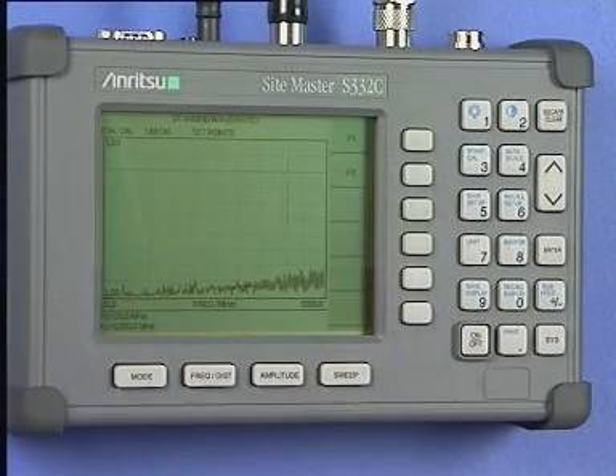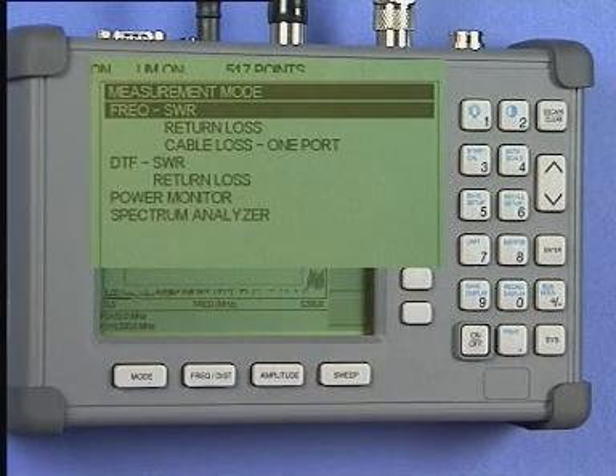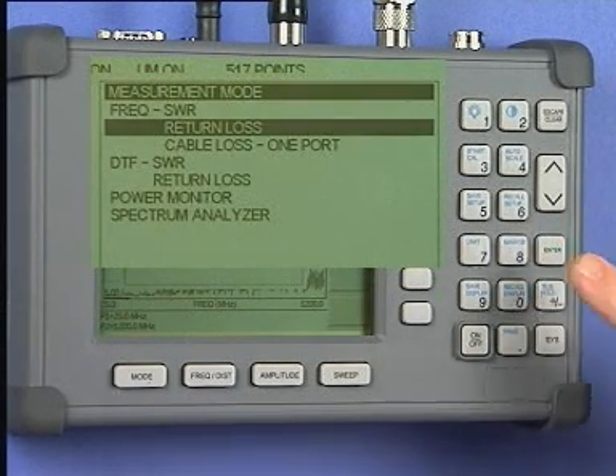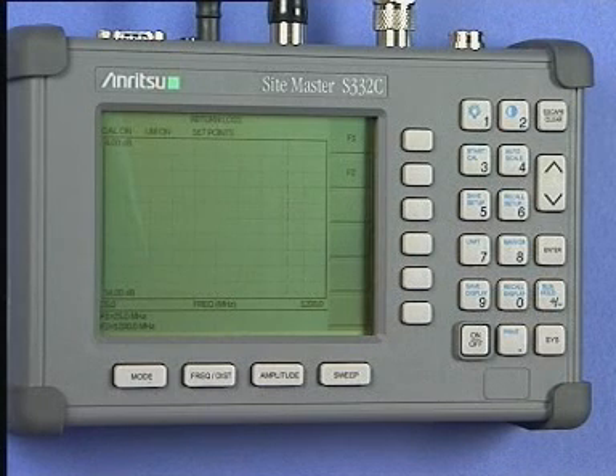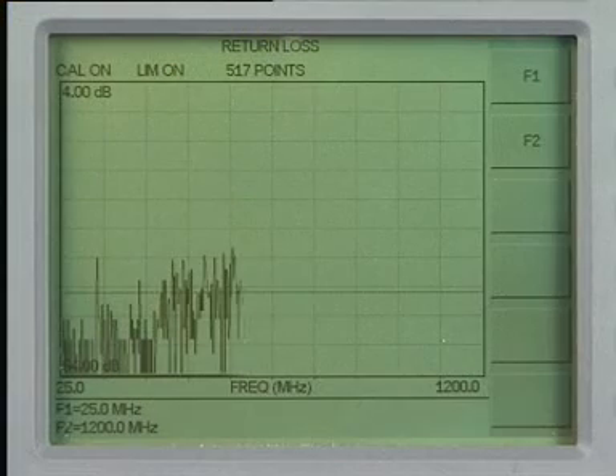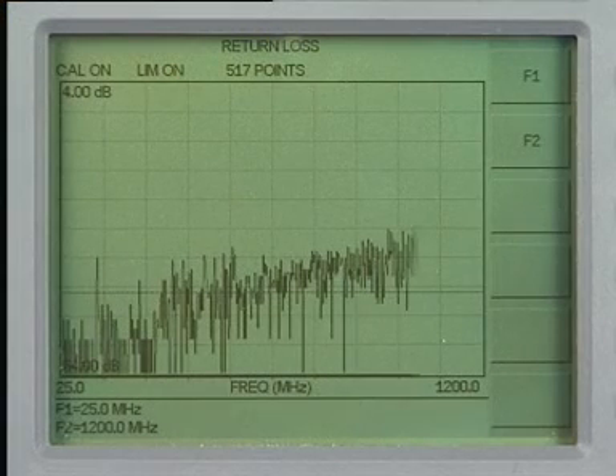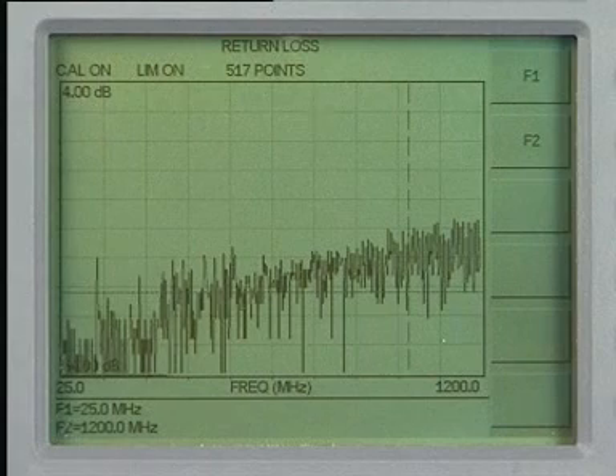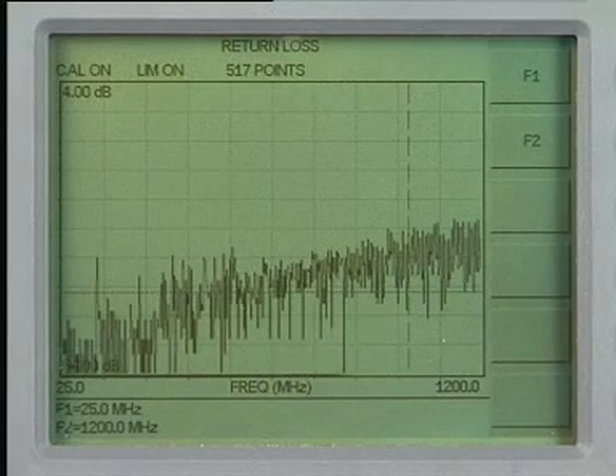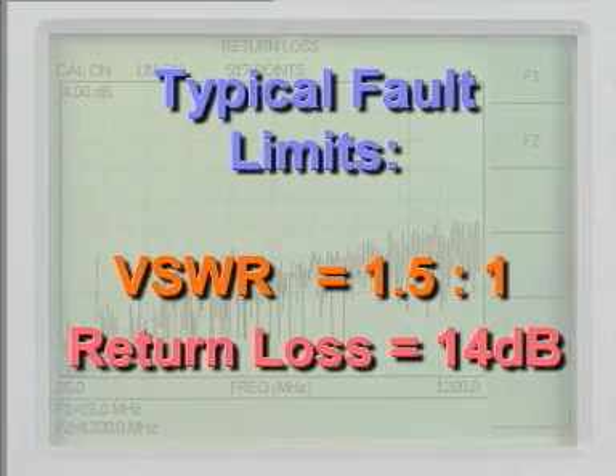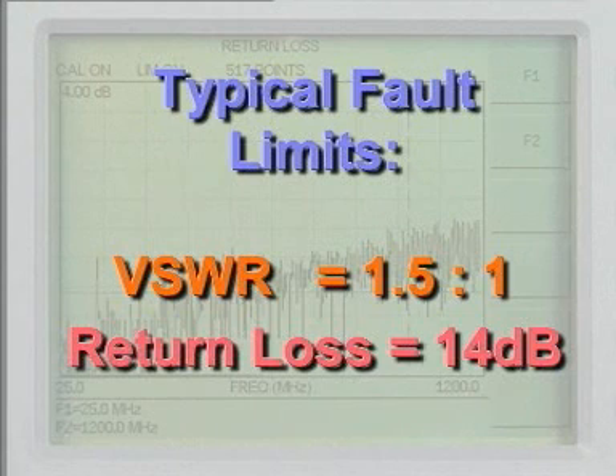To measure the return loss, press the Mode key. From the menu, select Frequency Return Loss and press the Enter key. The instrument will display the return loss graph. Your system planners or engineering department will have stated the failure level. 1.5 to 1 or -14 decibels is a typical failure boundary.